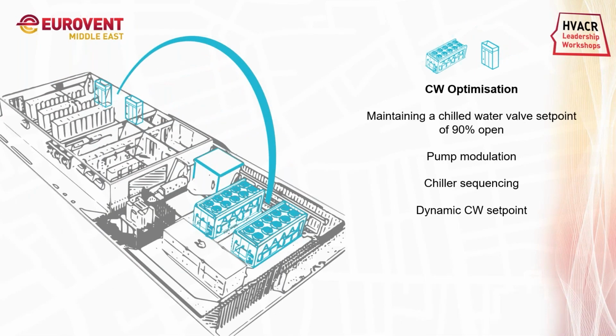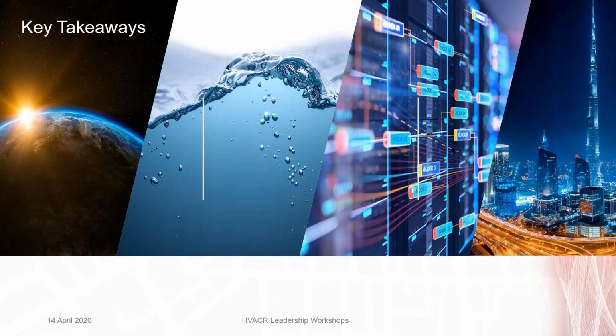Now on the chilled water optimization, we maintain a chilled water valve at 90% open by a dynamic chilled water set point. So when we have a stable system load, say the chilled water valve is open 40%, we can have the chilled water valve open at 90% and use a higher chilled water temperature at the chillers and increase the efficiency there. And by pump modulation and chiller sequences, we can attain chilled water optimization.